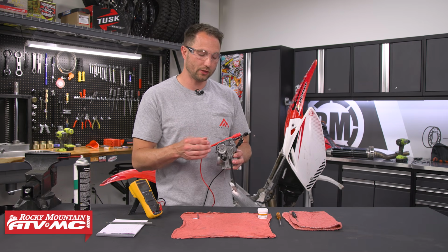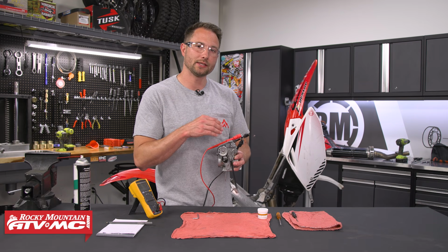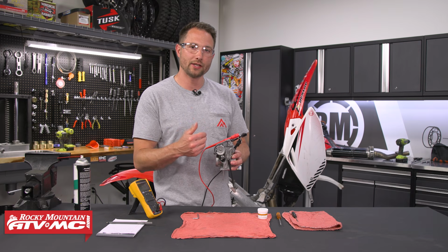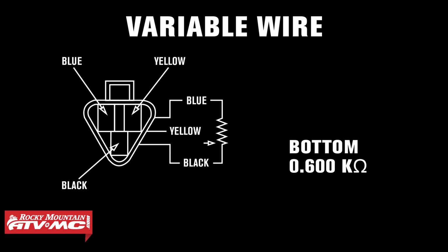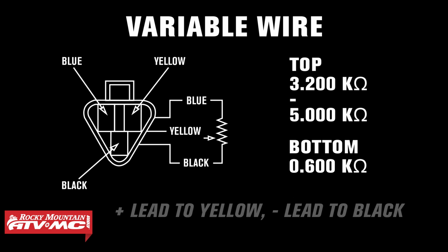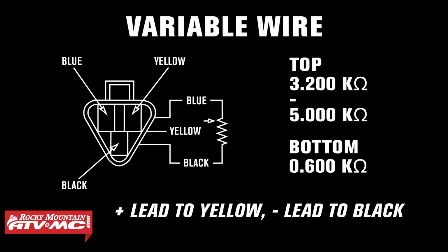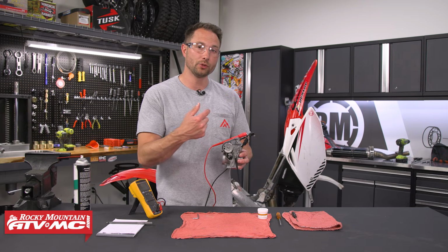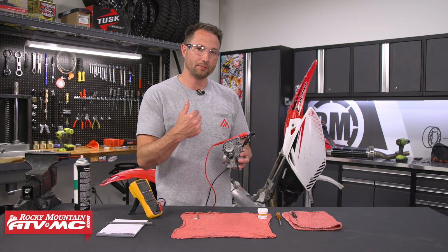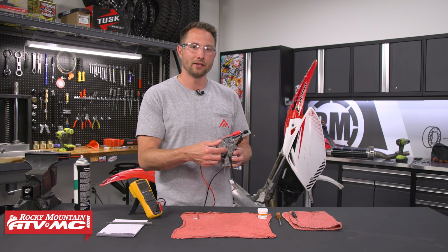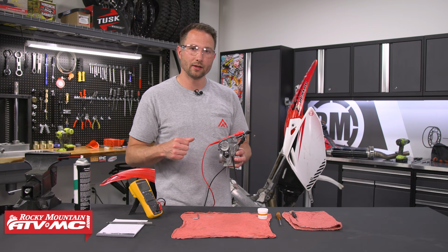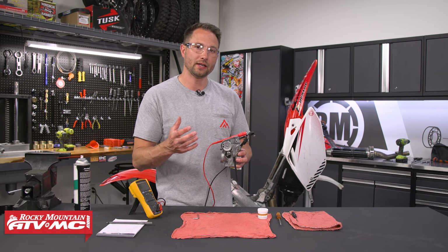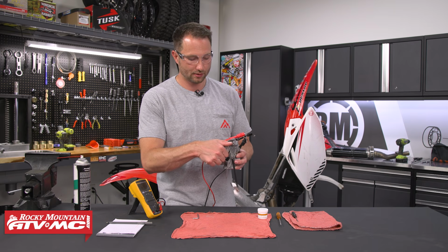Now the last check we can do is make sure that the resistance is good all the way throughout the range. So at the bottom, we're starting at 0.6 k ohms, and at the top, you're going to read anywhere from 3.2 to 5 k ohms. You just want to make sure that the numbers increase fairly smoothly all the way to the top, and then the same thing as you go down. If you have any weird dropouts in the numbers, then you know that sensor is bad and you want to get it replaced.